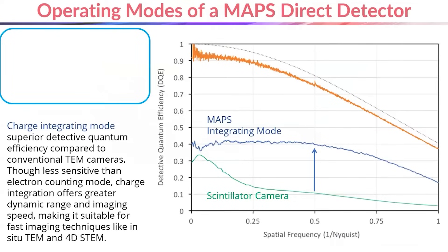MAPS detectors can be operated in two different imaging modes. The basic mode of operation is called integrating mode, in which the electrons incident on the detector generate a charge in each of the pixels and that charge is then read out as the signal to form the image. This leads to a significant boost in detective quantum efficiency, especially at high spatial frequencies compared to scintillator coupled cameras, which allows MAPS detectors to collect information with greater spatial resolution for any given electron beam dose.